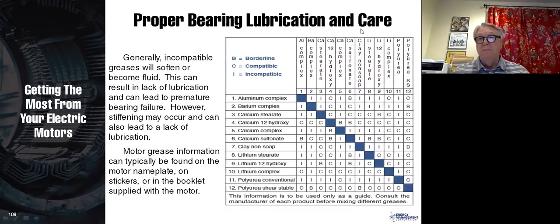So polyurea has become the go-to grease. But if you get a new motor, pretty much that's what you're going to get, assuming it's a greasable motor and not an oil motor. It has grease rather than an oil bath. But this is a table that is in your booklet, and it shows all the different types of greases and which ones are compatible with one another. And you can see a C would be compatible, an I would be incompatible, and a B would be borderline. So if you go down here to a polyurea conventional, you'll notice it's pretty much only compatible with itself.